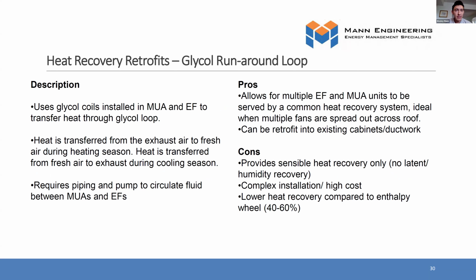Glycol runaround loop. This is an option for heat recovery where, as I mentioned in the previous case, you have equipment spread out all over the roof, and you don't have a central exhaust and central makeup air right next to each other. This could be an option. This is essentially using a glycol coil. So we have piping running around the roof, connecting each unit together with a coil that we would retrofit into the existing units or new units.